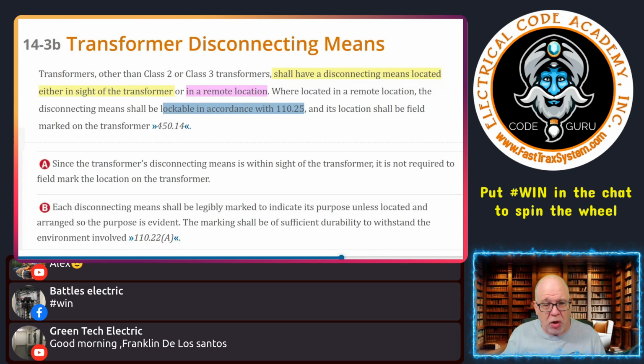If I'm going to do a remote, so my primary side disconnect is not beside my transformer and it's remote in equipment upstream somewhere, then I have to make sure I do the labeling requirement. What's the labeling requirement? It requires me to put a label at the actual transformer to let me know where that disconnecting means is located. And that's all covered in 450.14.